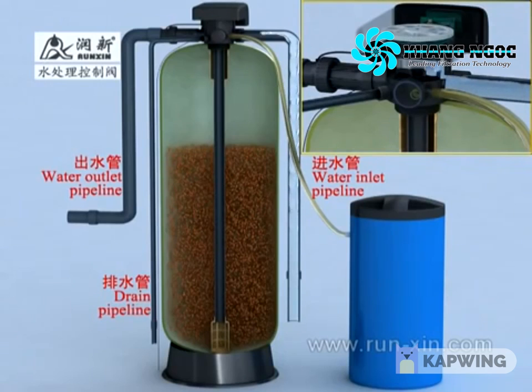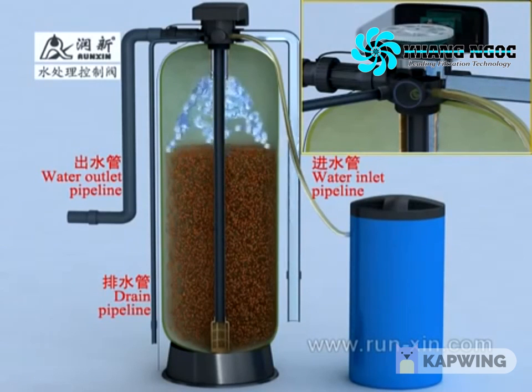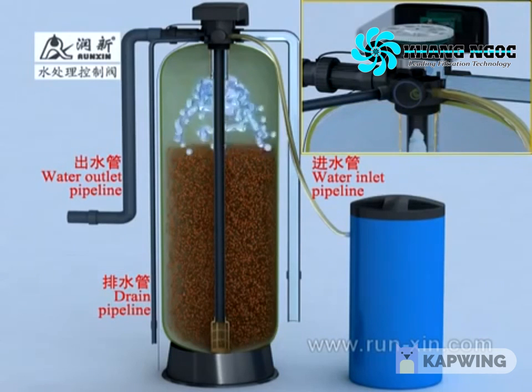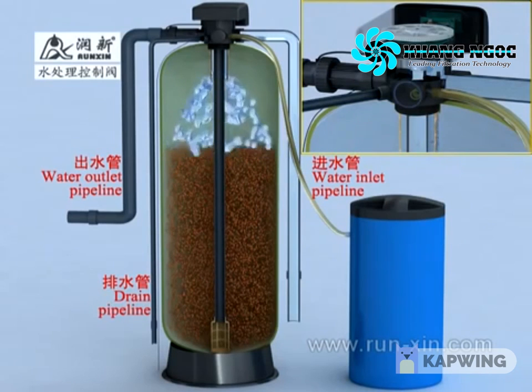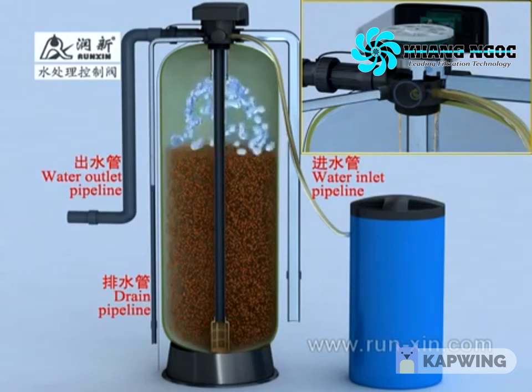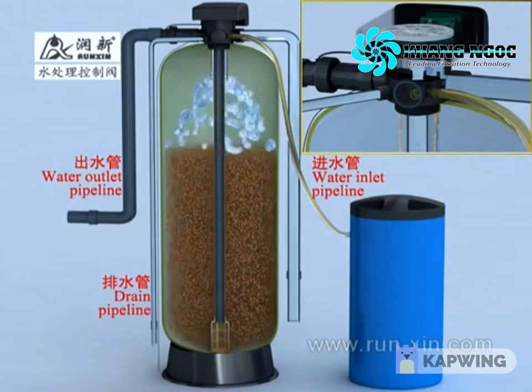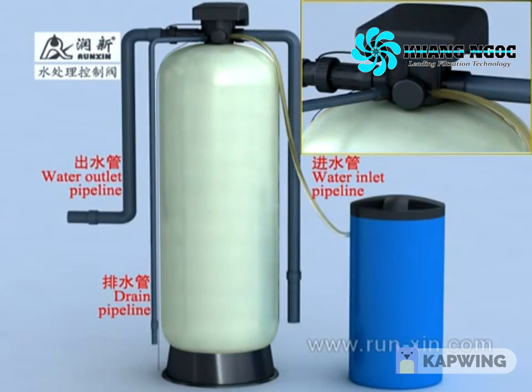Raw water flows into the control valve through the water inlet, from the top of the valve core to the valve body, through the top strainer to the tank, then past the bottom strainer to the riser pipe, and finally through the valve core. The residual brine is discharged from the drain outlet. When fast rinse reduces to 0, it is over. The system enters into the service state.